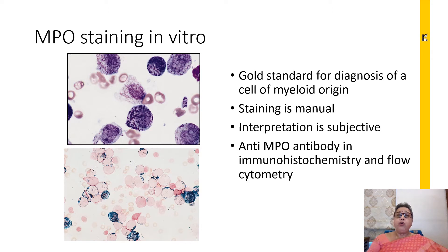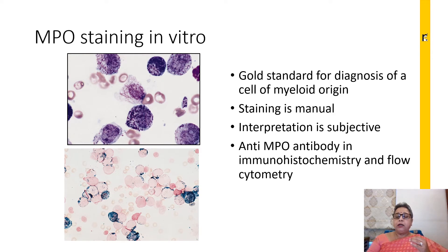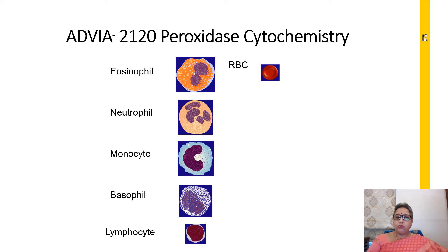If we were going to use this cytochemical stain in our cell counters to definitely identify a cell — both for differentiation of blasts and for accurately finding the differential counts — that would be an added advantage. And that is exactly what the Advia 2120 does in its WBC scatter. To identify WBCs it uses a dual technology: the cytochemical stain using myeloperoxidase, followed up by flow cytometry.